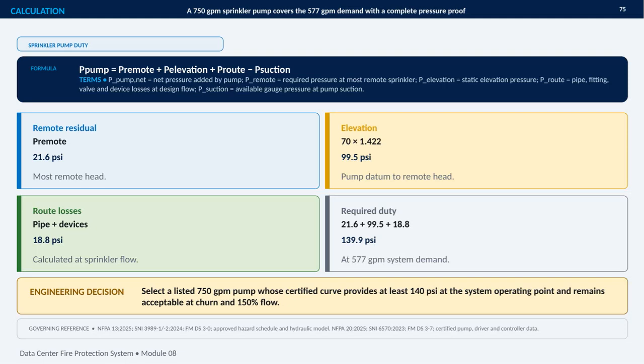This slide shows the sprinkler pump duty calculation for the data center fire protection system. The key question is how much net pressure the pump must add at the design flow. The calculation combines 4 terms: the required residual pressure at the most remote sprinkler, elevation pressure, route losses through piping and devices, and any available suction pressure. Here, the remote sprinkler requires 21.6 psi. The 70-foot elevation difference contributes 99.5 psi, using the stated conversion factor, and the calculated pipe and device losses add another 18.8 psi. With no suction pressure deduction shown in this summary, the required duty is 21.6 plus 99.5 plus 18.8, or 139.9 psi, at a system demand of 577 gallons per minute.